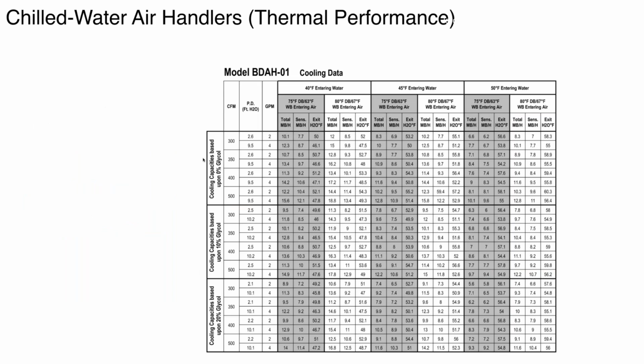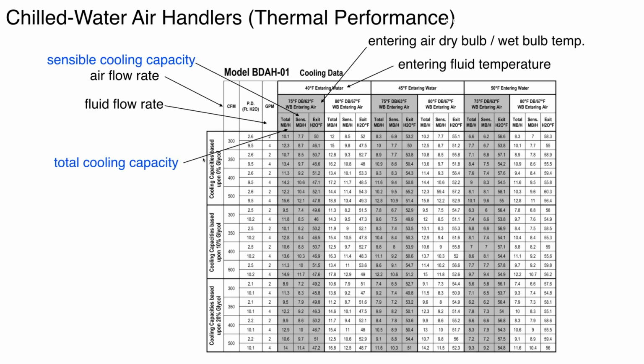Now, rating data on air handlers. I don't want to go into great detail, but there are quite a few different ratings here, both sensible cooling capacity and total cooling capacity. Latent cooling capacity isn't listed, but if you subtract sensible from total, you'll get latent. This shows different entering water temperatures. The colder the entering water, the higher the cooling capacity, the numbers that you see down here. Different fluids, different flow rates. The higher the flow rate going through the coil, the higher the cooling capacity is going to be. So it's a typical rating sheet. And after you've done the cooling load calculations and you know what your sensible and latent cooling loads in a given space are, you can start to look at data like this and select a unit that has approximately the same capacity.